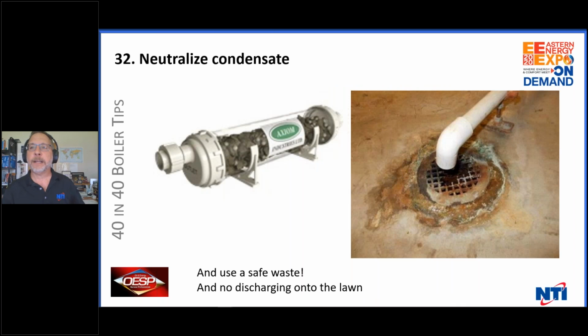Neutralize your condensate. For God's sake, please neutralize your condensate. We have measured condensate pH down to 1.6. This is extremely acidic. A beer is 5.2 and will erode the top right off a tile, take the concrete right off down to stones. That's 5.2. Muriatic acid is 0. We're really close to that, aren't we?